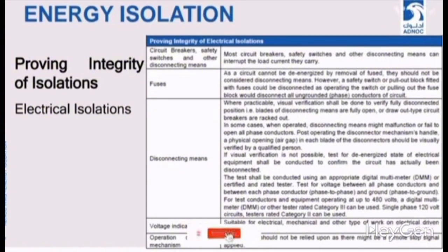Next, we come to the point of fuse installation. If we have any power supply and we have installed a fuse in it, we will place any fuse in series. If we need its physical isolation, we will physically remove the fuse from the circuit to isolate it from the power supply line. If we remove it, we will get additional support against the breaker, indicating that our breaker is also off and we have removed the fuse as well. We have the integrity of electric isolation 100% safe. The next step will be, what does disconnecting mean? We had turned off the breaker.